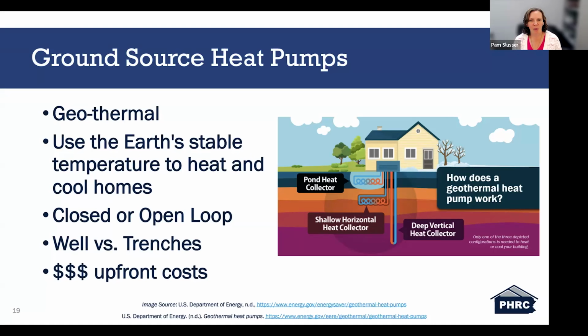A closed loop is a water refrigerant based system. It's circulated through pipes or tubes underground, collecting heat from the earth and carrying it through the system and into the building. In the summer, it reverses, pulling heat from the building and placing it in the ground. It's a little bit more expensive to install due to installation requirements, however, more efficient if done correctly. The open loop is the same basic principle as the closed loop operation. However, this needs to be installed where an adequate water supply is available and you have open discharge. So the open loop is pulling water in, but then it's discharging as well.